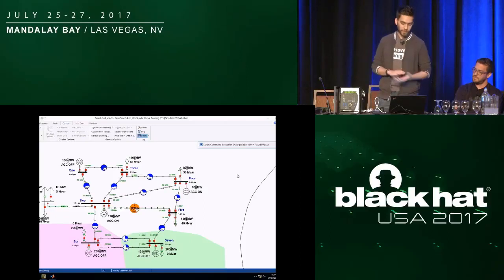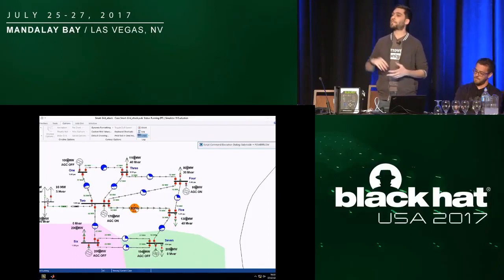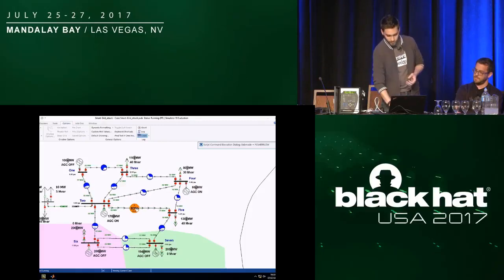We can see that on the parallel simulation, the circuit breaker controlling that 10.7 megawatt load is now open in the simulation model. And we can also see the increased strain on some of the power lines, or the difference in the power flows.